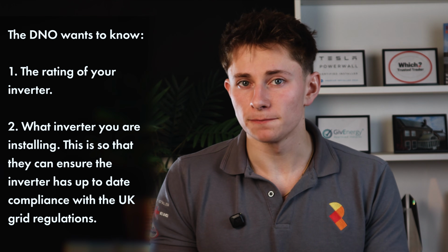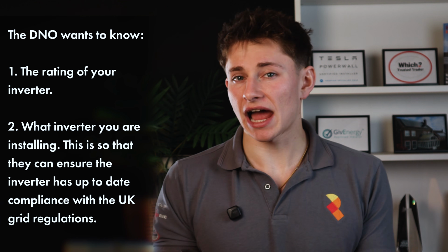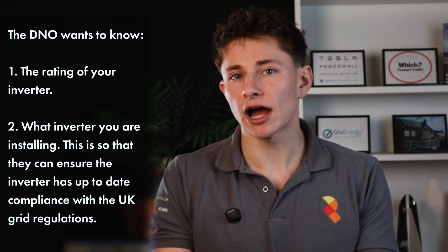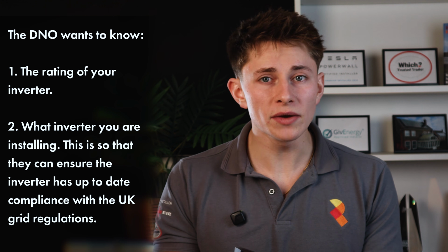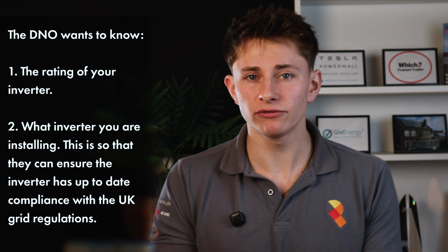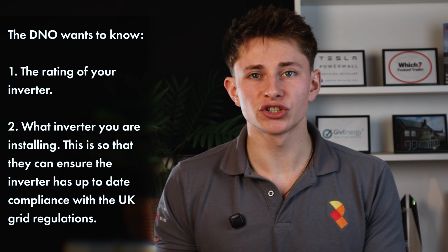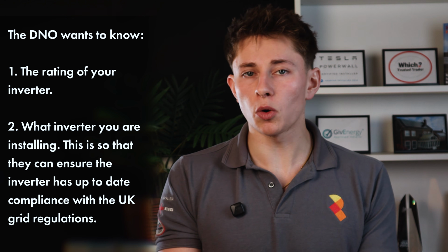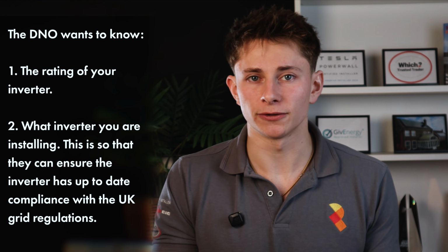So what does the DNO actually care about, and what are they looking at on your application? Well, this is quite straightforward. The only thing they care about at residential scale is the rating of your inverter. That's all. They don't care how many panels you have, they don't care how big a battery you have. All they want to know is what is the rating of the inverter and what is its potential to export. And this is what we have to disclose on the application.